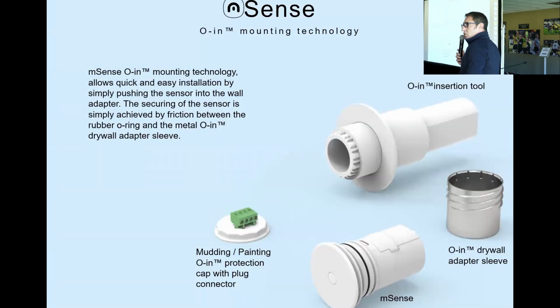How do we install the sensor? So the sensor has this very cool technology. It's called O-in, O for the shape, the round shape. And basically, you make a hole in the gypsum, and then this adapter sleeve is attached to this insertion tool, and then you screw this sleeve, this shroud, into the gypsum. And then you can slide in the sensor, and you see there is a rubber ring here that will hold the sensor in place.